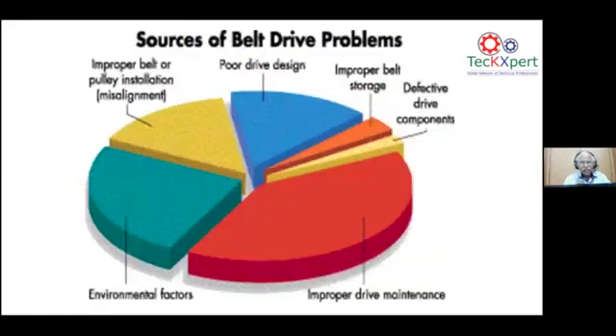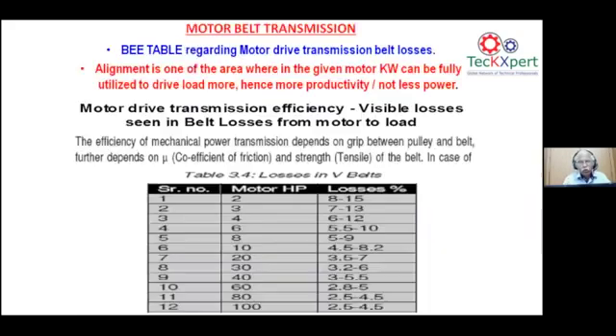So belt drives have their own problems, like poor drive, improper belt, defective drive components. More than that, improper drive maintenance and the environmental factors. These two are playing the major role. And here we find, if we are able to replace the pulley drives once in 4 years, let us say once in 40,000 hours of continuous running, this will definitely improve. A glossy pulley drive, where it is looking very shiny and with no grip, this is going to be the loss, and the productivity loss is more as such.